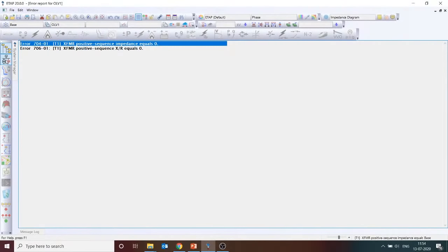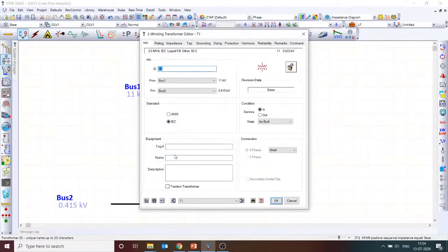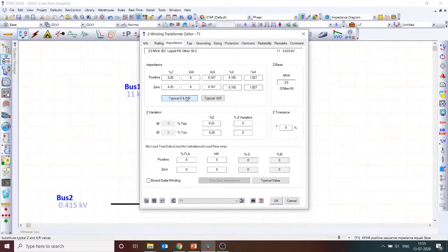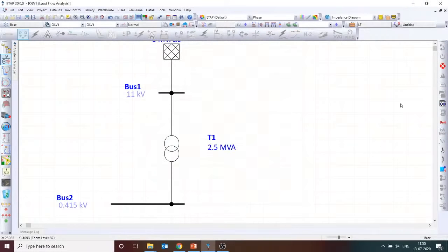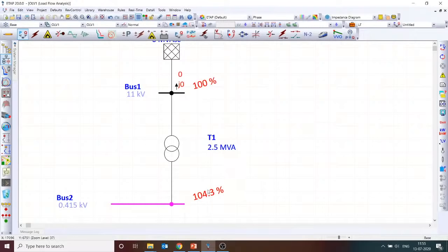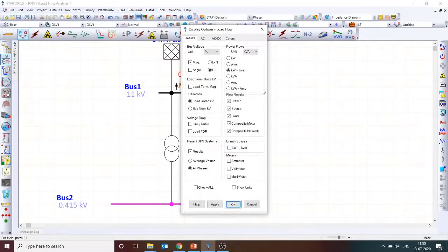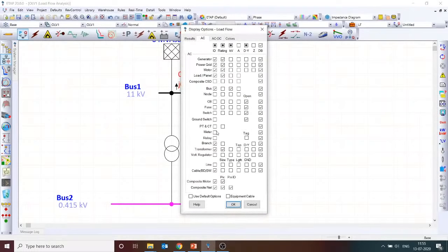Because I have not given the transformer impedance, I am just using a typical impedance of the transformer. If I run a load flow, it will run. So here the voltage is 100%, and here the voltage is slightly more than 100%, because the transformer voltage is slightly higher than the voltage of the 415 volt bus.